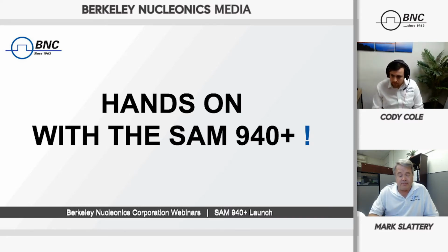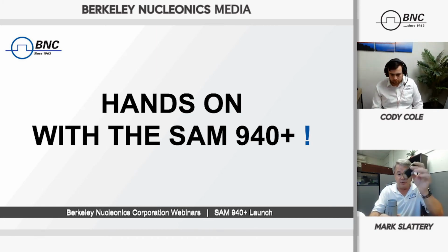I'll tell you what I did not cover in this little flurry of activity, and that's the basics. I always promise to show the basics to people that are training or getting acquainted. One of them is to make sure the device is turned on. So always remember to put the battery in, and always remember to lock the battery in place. You turn the device on with this orange button on the side, press and hold it. If you press and hold that a little longer, the orange LED will tell you that you've engaged and that the power is on. It takes a little while for the screen to come up and boot up, but it will eventually.